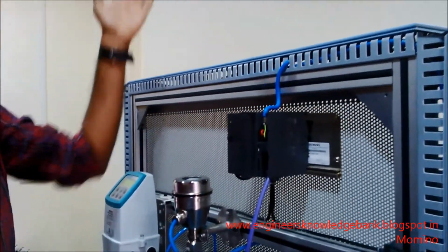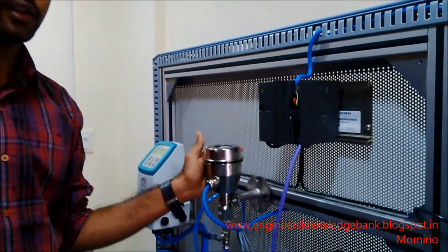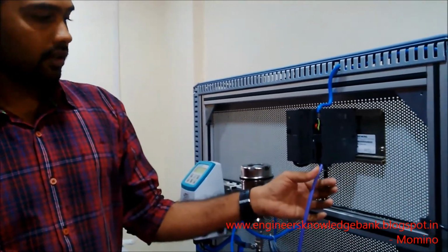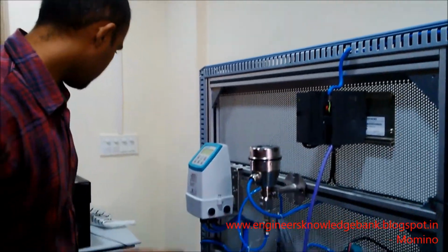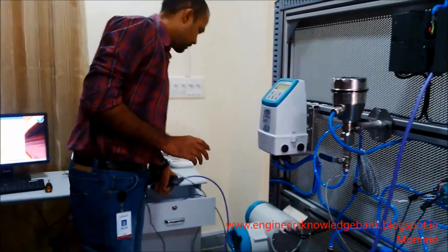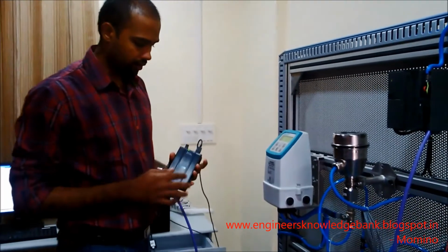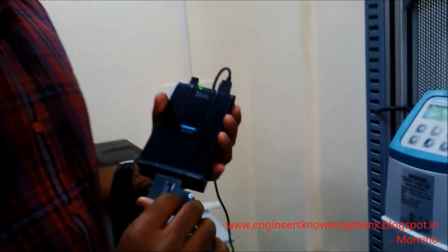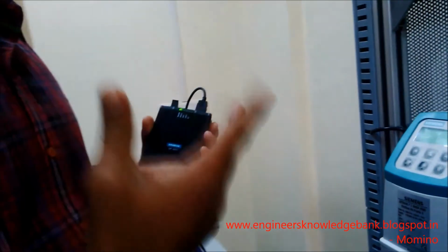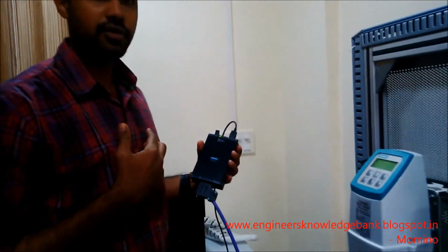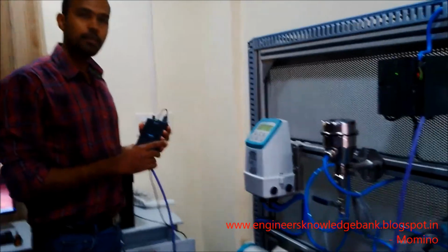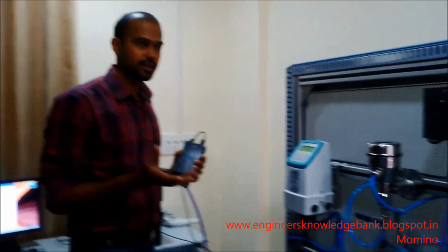The devices connected to PA are, one, a P300, and I will also show an LR250 later on. This is a DP cable which is connected with the help of a CP5711 modem. This purple cable is the DP cable, which is connected to the coupler, and through the coupler the PA cable is connected to the process instruments that need to communicate with the PC. These are the hardware requirements necessary for communication.